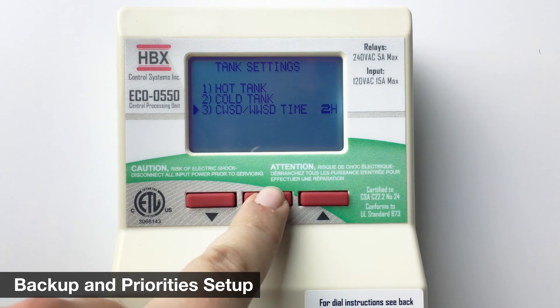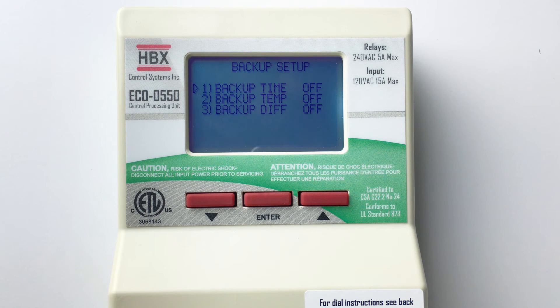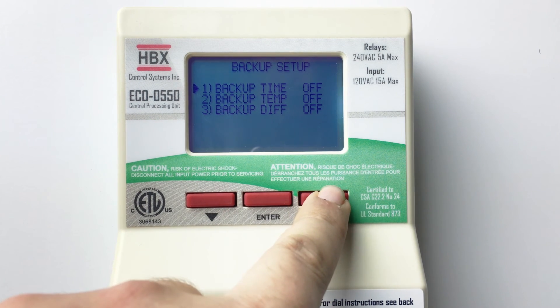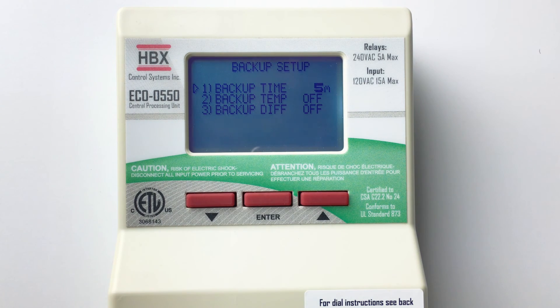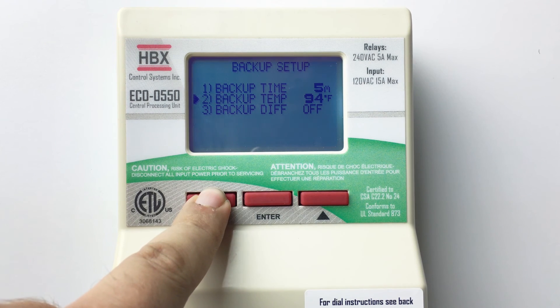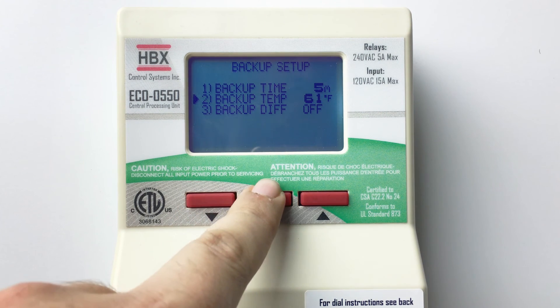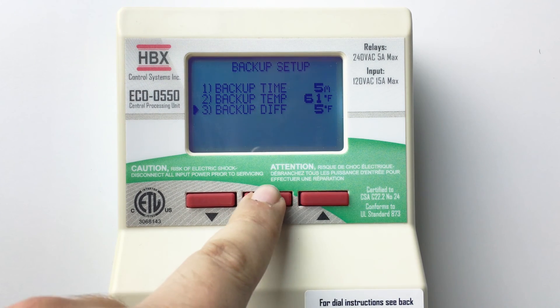Hold the enter button to return to the setup menu. Select backup. Here we can adjust the settings for a backup boiler. The backup boiler can be configured with several settings that can be used independently or in conjunction with each other. Backup time is the minimum lag time in minutes between the last stage firing and the backup boiler being enabled. Backup temperature is the desired outdoor air temperature required before the backup is allowed to come on. Backup diff is a differential set on the tank at which you want the backup to be enabled.